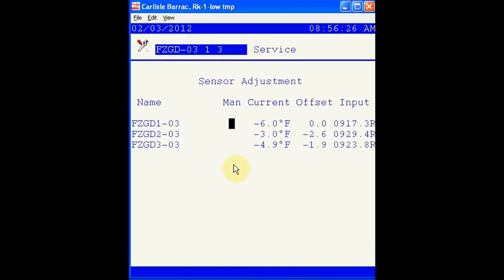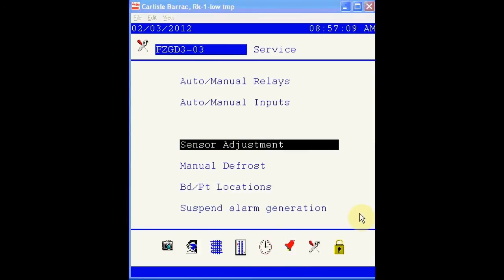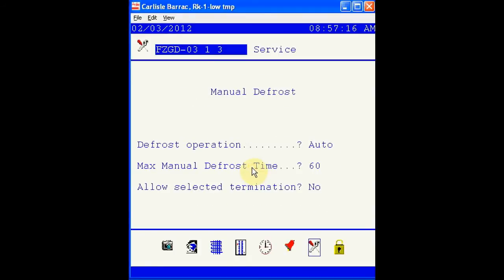The sensor offset screen is available much like the rack we looked at, to allow offsets to be placed for cases and to view input information. Let's say we needed to defrost a case using what's known as emergency defrost. Select manual defrost and you'll see your options for this case. The defrost operation can be changed from auto to manual on or manual off. The maximum time can be adjusted here if a defrost is needed that is longer than the normal defrost time. And here you can select whether or not you want to terminate based on time or other termination options normally afforded to the case.